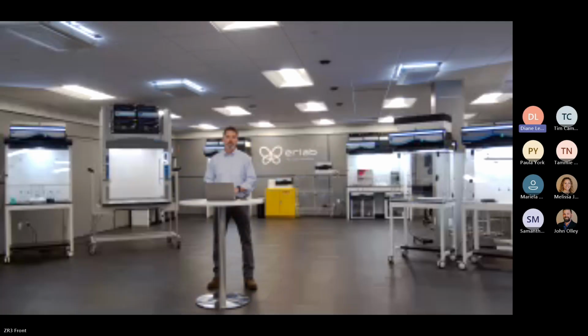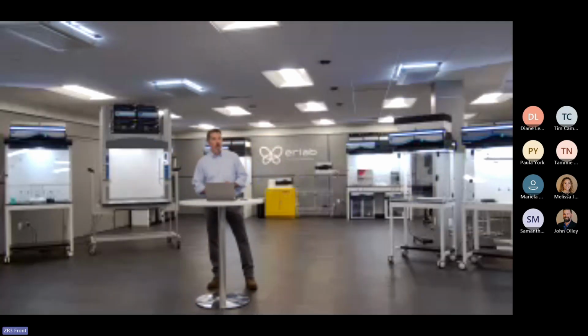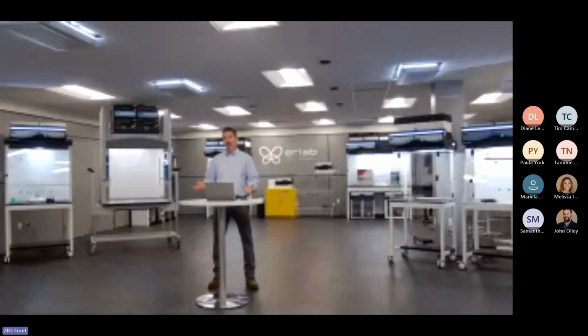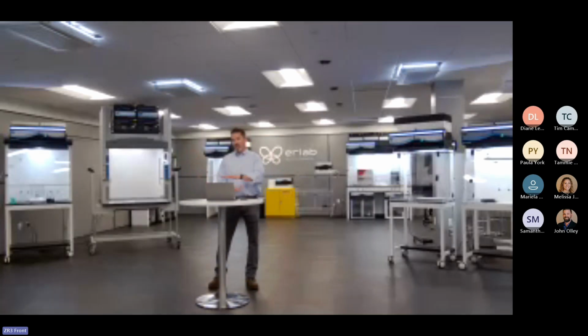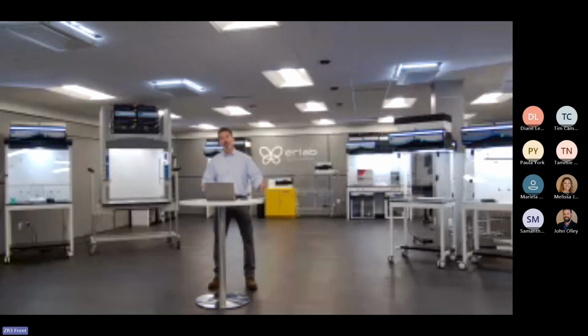Looks like we got a question in the chat. How do I dispose of the filter? So the filters are deemed regulated non-hazardous waste. If you have an on-site hazardous waste collection company, typically they can dispose of it for you. If not, when you order the new filter from us, it gets shipped by UPS in a box in a bag. Basically, you can take that filter, put it back in that bag in the box, and ship it back to us. Obviously, we need a PO for it, but you can ship it through UPS.